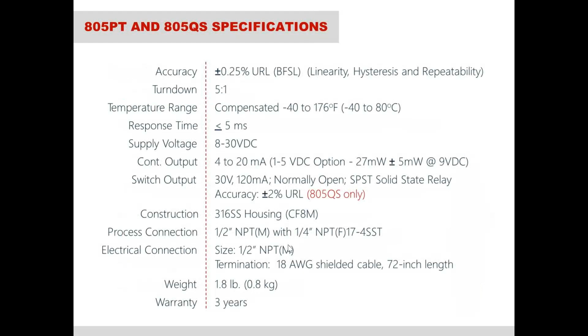Some of the specifications: the accuracy on the 805 is 0.25% of the upper range limit. It has a 5-to-1 turn down. The response time is less than 5 milliseconds, and then it also comes with a 3-year warranty.